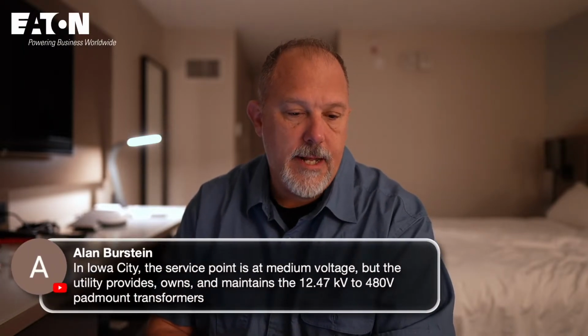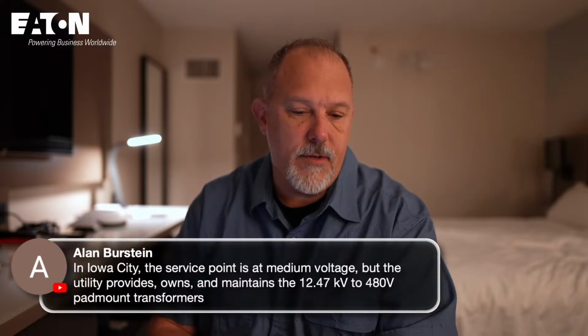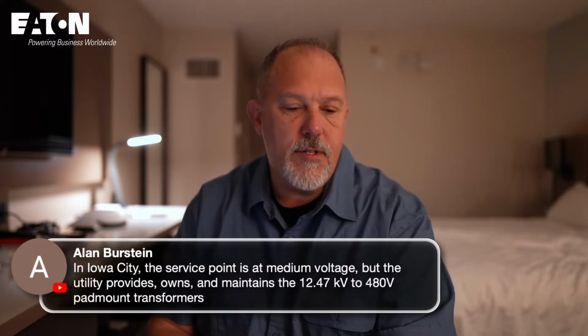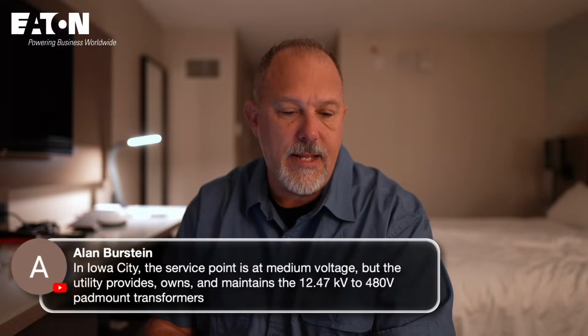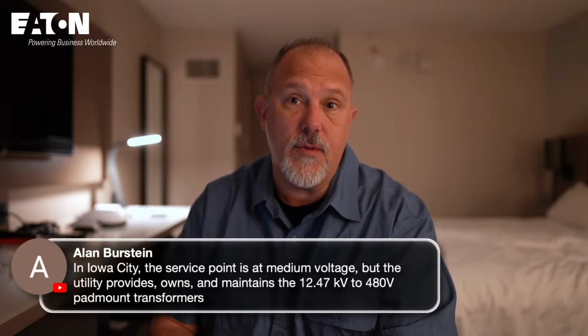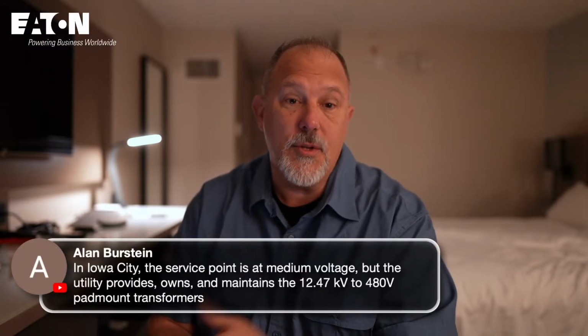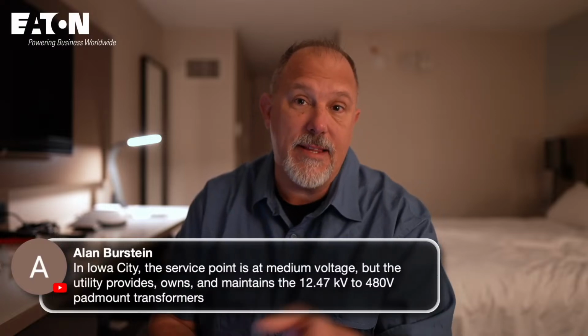So I wouldn't call those outside the NEC. I still say they fall under the rules of the NEC. In Iowa City, the service point is at medium voltage, but the utility provides, owns, and maintains the 12470 to 480 pad-mount transformers. That's the exact scenario he was talking about. So what codes do we follow for those transformers? The NESC or the NEC?